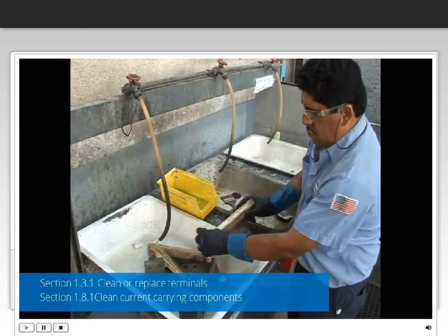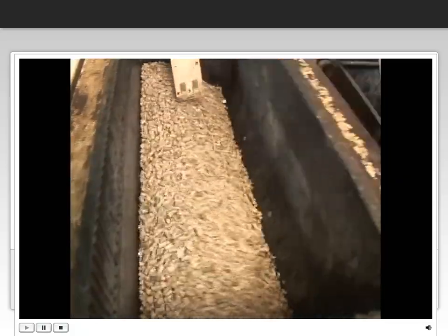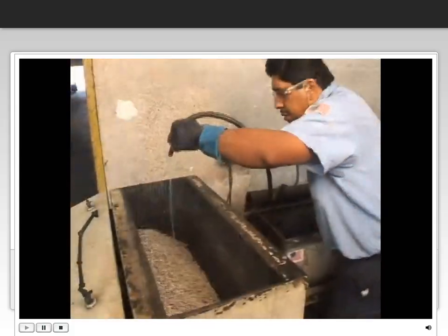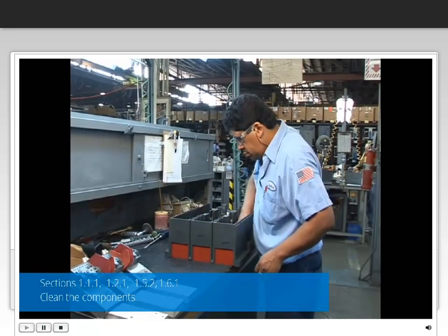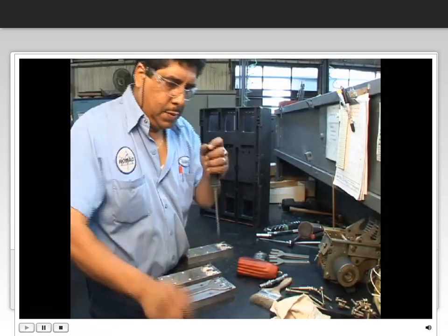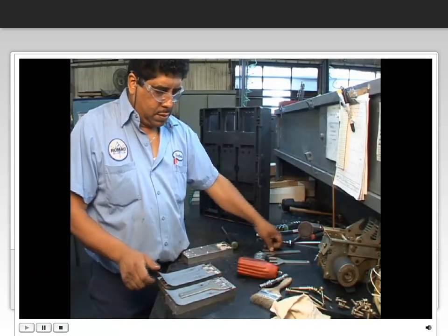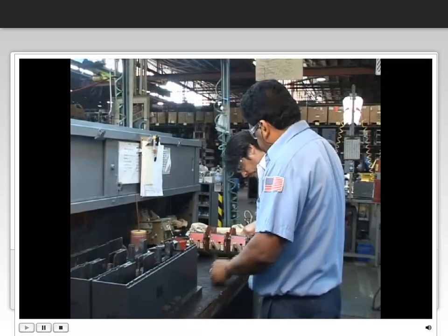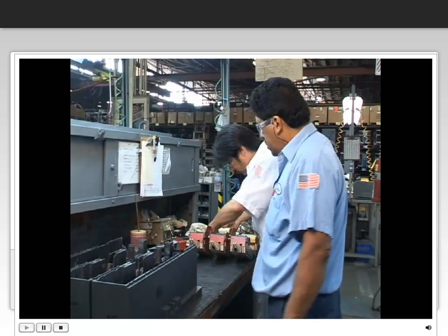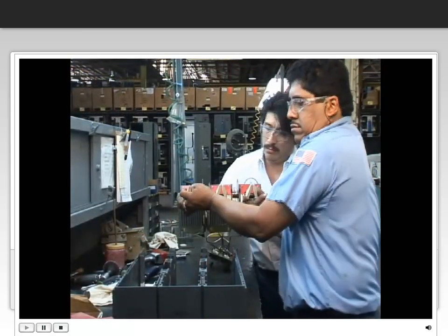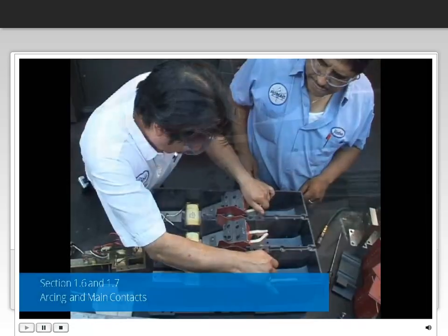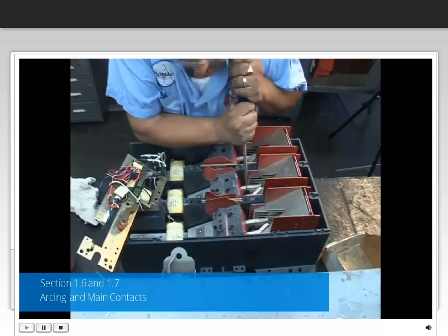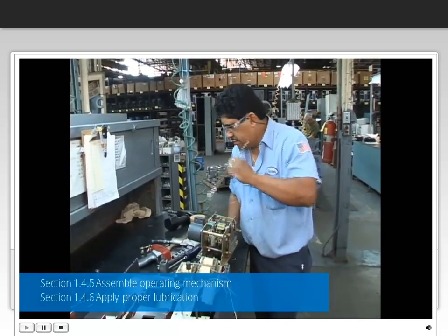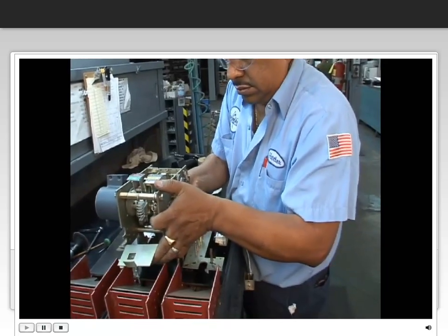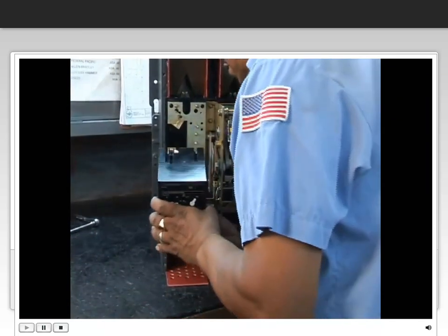All metal parts are then placed in a vibratory cleansing system for cleaning and polishing. The case, cover, and all insulating parts are cleaned and surface treated as necessary before the reassembly begins. First, the various contact parts are reassembled into the contact subassembly. The main stationary and moving contacts are being reinstalled into the breaker. The moving parts are checked to make sure they are not binding. The cleaned and lubricated pawl and ratchet assembly, followed by the trip unit mounting plate and the trip unit, are reinstalled.